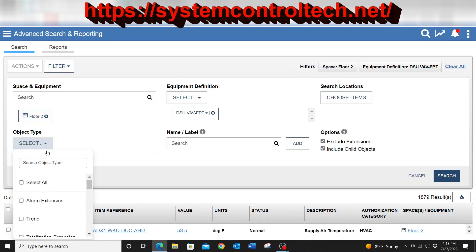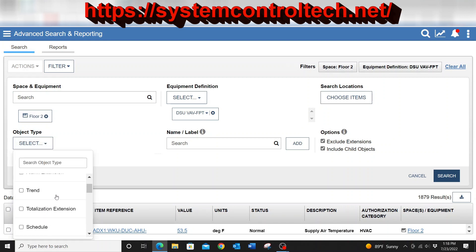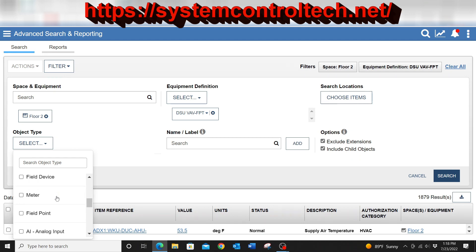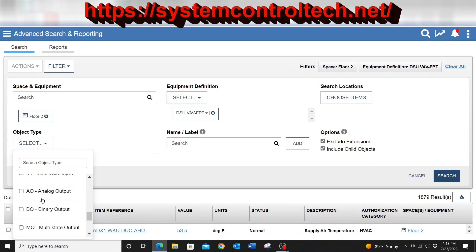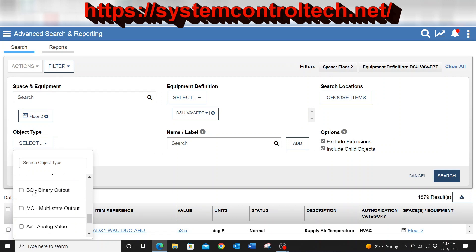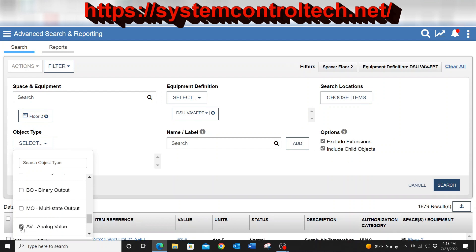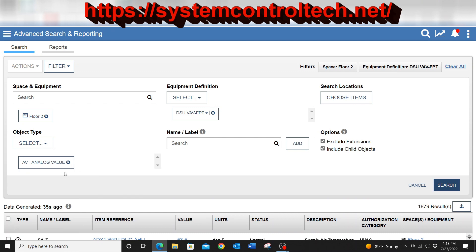The object type, since this is going to be a temperature set point, the particular object type for this is going to be an analog value. So I can scroll down through here just to filter it down as much. You can see I have all of the different types of values here. So I'm going to select analog value from the list. That will add that into the search criteria.